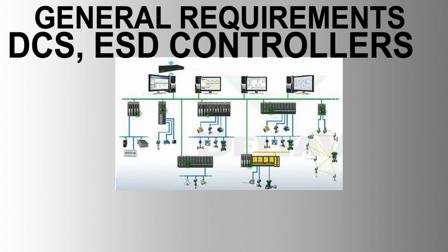General requirements for Distributed Control System DCS controllers. 1. Types of I/O cards. Analog input AI cards, designed to accept 4 to 20 mA DC signals with a maximum input resistance of 250 ohms. Capable of 1 to 5 VDC input option with input resistance equal to 500 k ohms or greater. Input faults such as open circuit and short circuit are detected by the I/O module.